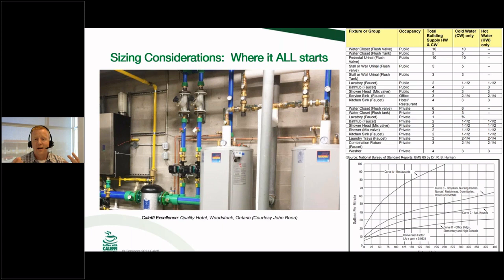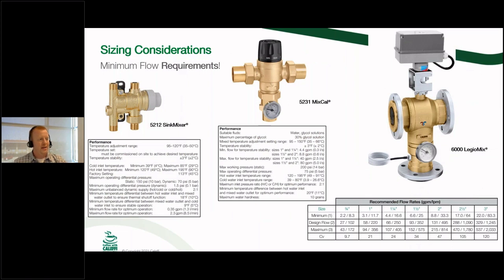So you're sizing this based on maximum flow requirements, and chances are you're oversizing it to begin with, which leads you to a whole other problem. Okay, obviously you want to size it appropriately to make sure that you're meeting the maximum requirements for that building. Chances are you're going to be oversizing it, but the thing you need to remember is minimum flow requirements. Okay, this is the phone call we get probably more than anything, the dreaded phone call. The one that scares me the most is where somebody says on the phone, and gladly we don't get too many of these, but they start the conversation off with, I've replaced this valve 3 times and it's still doing the exact same thing.